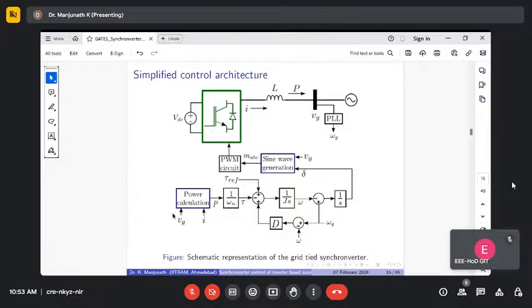Whatever current is injected into the grid, multiplied by grid voltage, will give you power. Upon dividing power by omega, the angular frequency, you get the torque component. So reference torque from reference power, actual torque from actual power, and the mismatch is given to the 1 by JS block, which gives frequency.